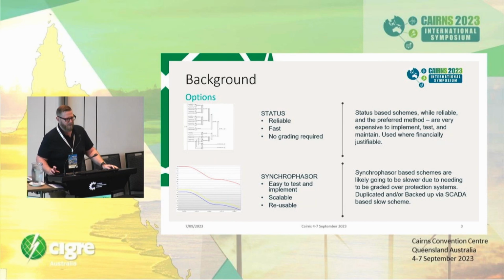And when we looked into it a bit more, I think some of our brethren from the southern states had looked at synchrophasors and anti-islanding and had implemented some kind of anti-islanding themselves. So that was the approach we decided to look at, and we originally ran a trial of just a straight point-to-point anti-islanding scheme. And I guess compared to a status-based scheme, you're looking at the system dynamics, so your synchrophasor scheme is going to be slower. You need to look at grading over protection. So if there is a fault and then the fault clears and everything returns to normal, you don't want to have tripped off a generator when you didn't really need to.